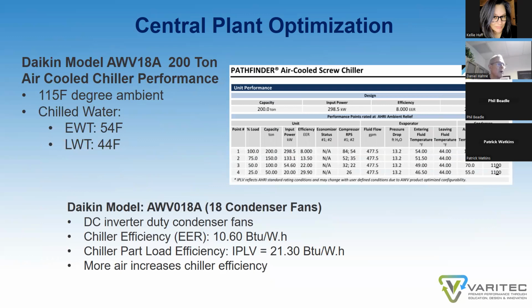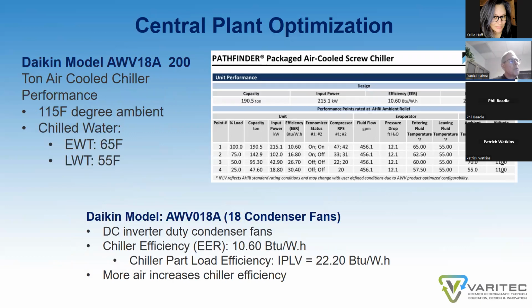We did a comparative analysis study using Daikin's new Pathfinder chiller, comparing how that chiller performs supplying 44-degree chill water that is used in a conventional HVAC system for dehumidification at air handler coils. And we laid out a configuration with 18 condenser fans, and the actual performance review showed that supplying 44-degree chill water results in efficiency of 8 EER and 21.3 IPLV. However, if you're able to supply 55-degree chill water, your EER jumps now to 10.6, your IPLV to 22.2, making this an excellent solution for adding another layer of efficiency to an HVAC system if you're using a DX 100% outside air solution that uses compressorized energy.